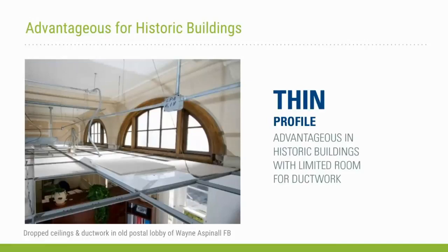Frequently, historic buildings have a variety of separate spaces that need individualized comfort control. VRF systems are well suited for these applications. They precisely control the amount of refrigerant flowing to each indoor unit and can include many indoor units of differing capacities and configurations. There's also the bonus of providing simultaneous heating and cooling when the system includes heat recovery. This allows the transfer of heat from one zone to another and reduces the operation of the outdoor unit, saving energy.